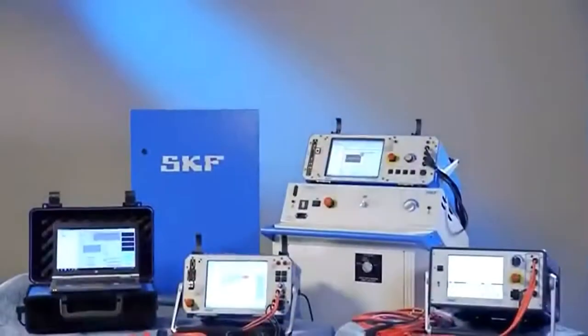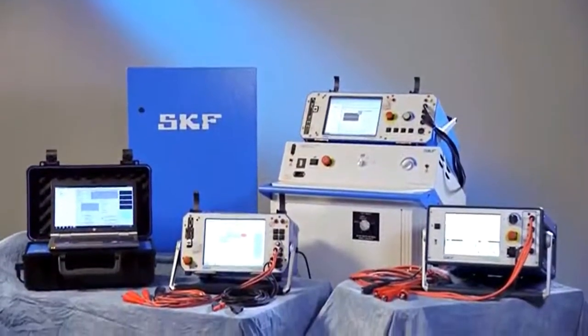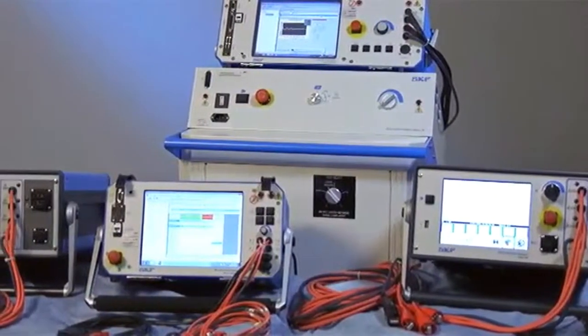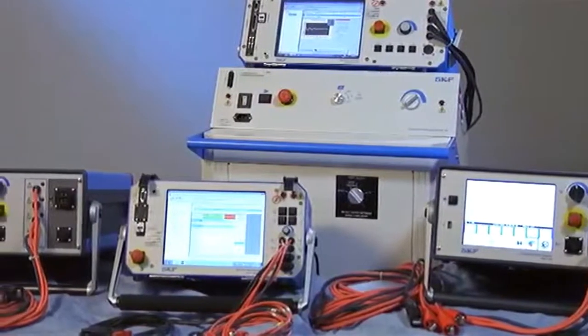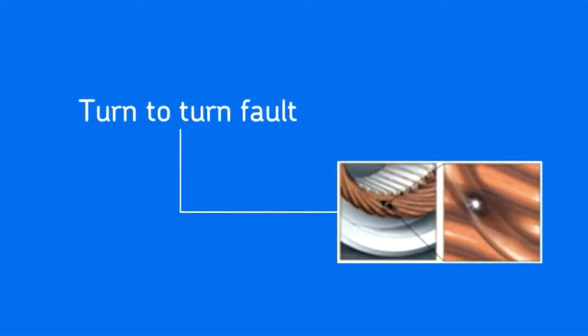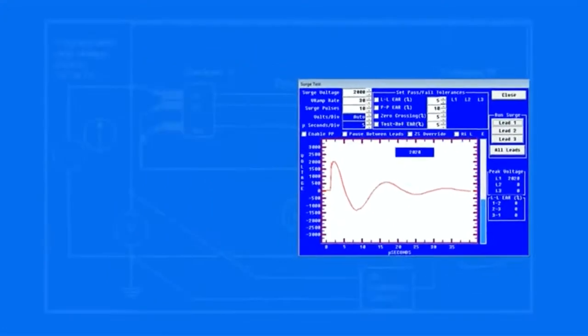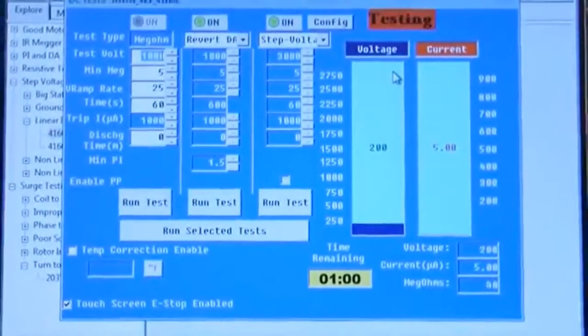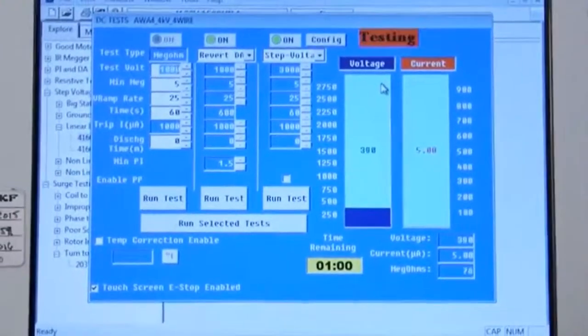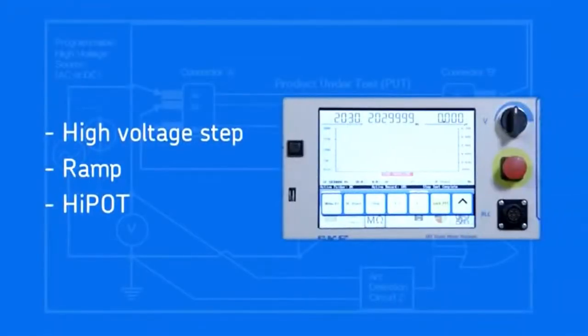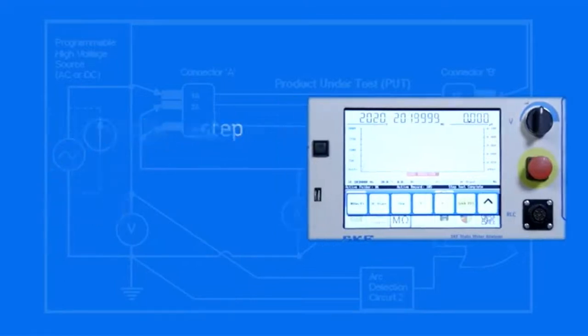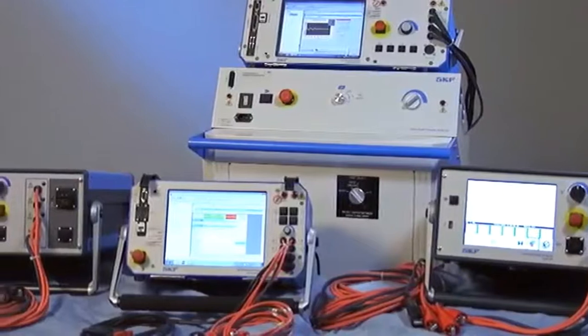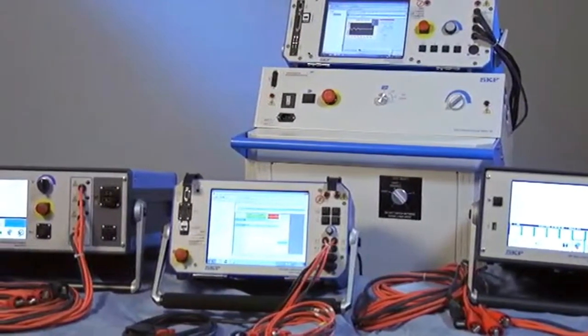SKF electric motor condition monitoring solutions completely address the faults not covered by vibration monitoring. SKF static motor testers completely assess the insulation system of the motor. These tests are run when the motor is off, disconnected from the AC power source. The most common insulation failure is between turns of wire that are next to each other in the same coil. This is called a turn-to-turn fault. The surge test is the only test that can reliably test turn-to-turn insulation. The surge test also finds phase-to-phase and coil-to-coil faults in the stator windings. Ground-wall testing is done with a meg-ohm test, but meg-ohm test alone is an incomplete test of ground-wall insulation. To completely test the ground-wall insulation, high-voltage step, ramp, and high-pot tests are also used. SKF static motor tests are non-destructive and follow IEEE and IEC motor testing standards for motor insulation testing.